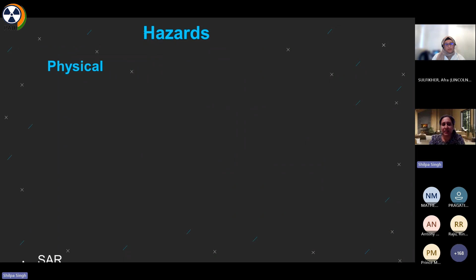First thing is SAR, specific absorption rate. What is specific absorption rate? When the patient is being given the radio frequency, which is a very strong electromagnetic field, and the RF coil is placed very close to the patient, the energy is converted into heat. If this heat deposited into body tissue becomes high, it can cause damage. But we don't have to face that. Why? I'll tell you. There are SAR limits already fixed.